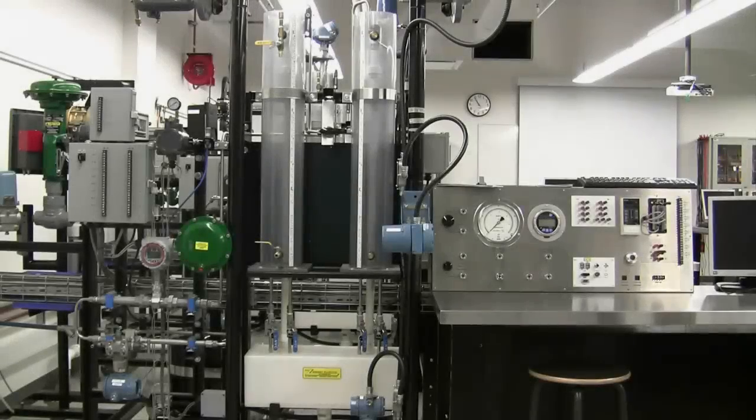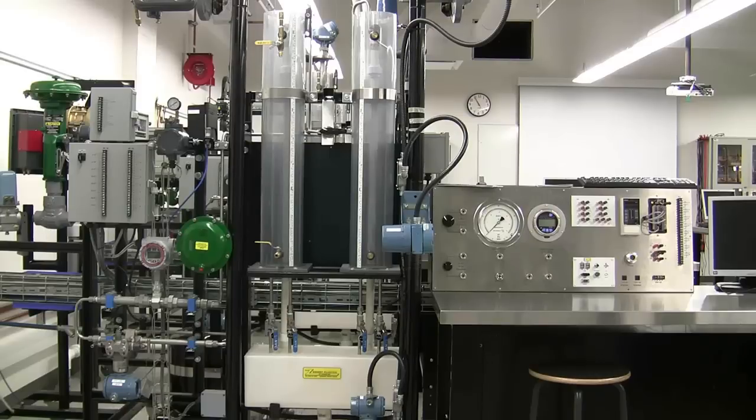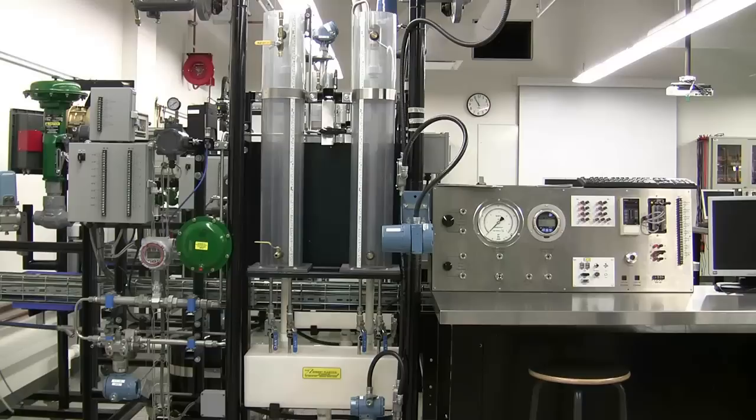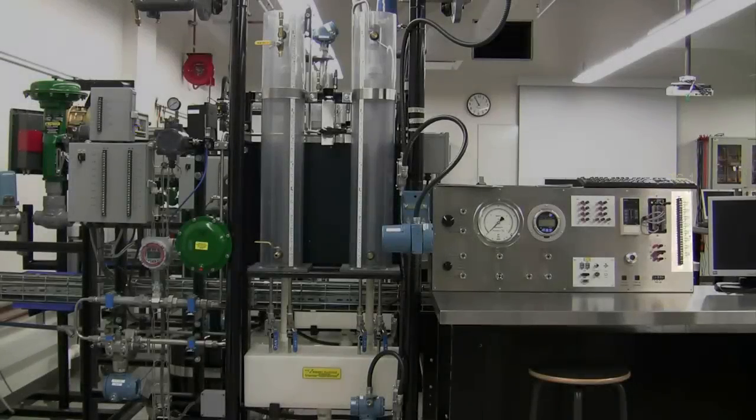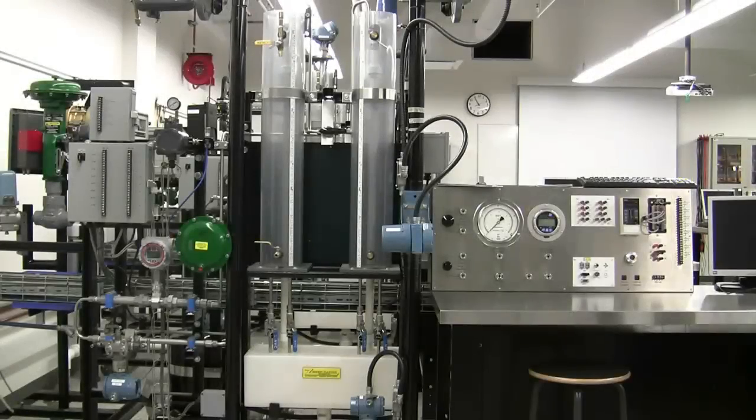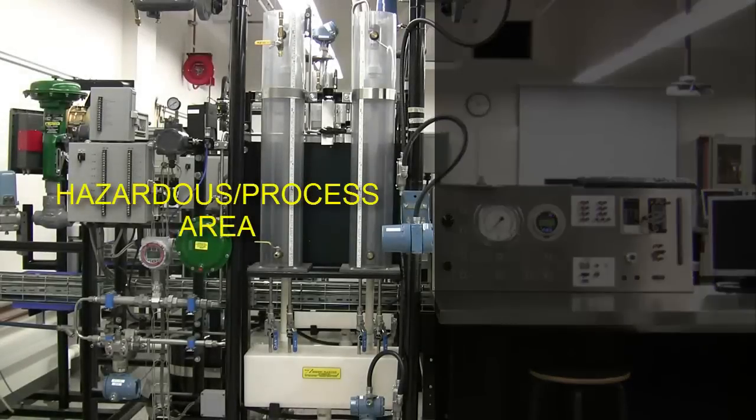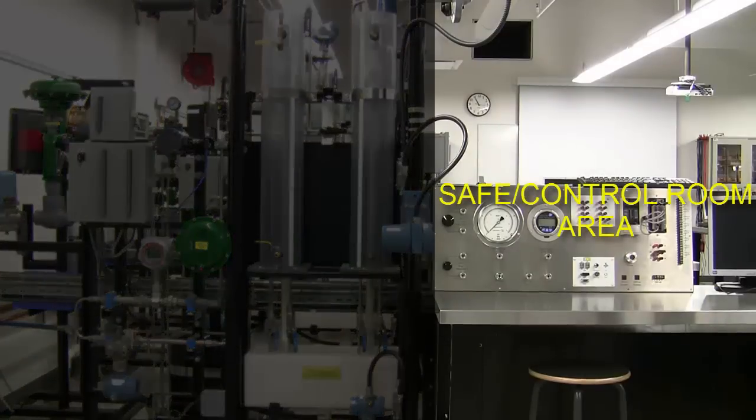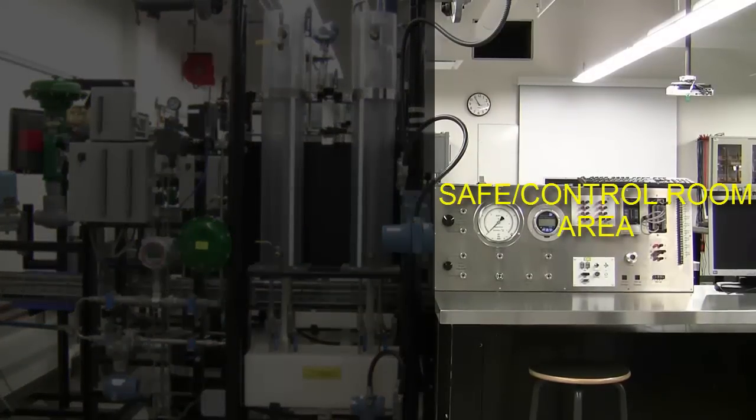The 24-volt power supply is mounted on the control panel and cannot be connected directly to the field junction box. A wiring path between the field junction box and the control panel has been provided. JB-1B on the field junction box is connected to TS-1 on the control panel. This layout is to simulate the hazardous side or process area versus the safe or control room area.